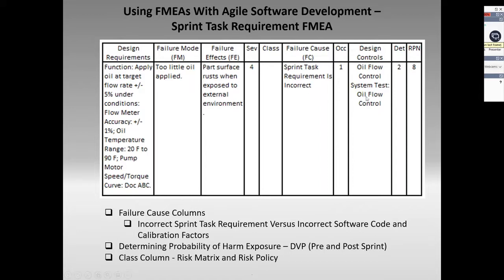This method here is not to prove that the code for the sprint task is written incorrectly, but to prove that you set the sprint task correctly. A requirement like this could have tolerances on it, so you need design controls in place to properly specify these. These sprint tasks could also have hardware limitations, because the people writing code need to understand what's expected, what hardware they'll use, and the variation in that hardware.